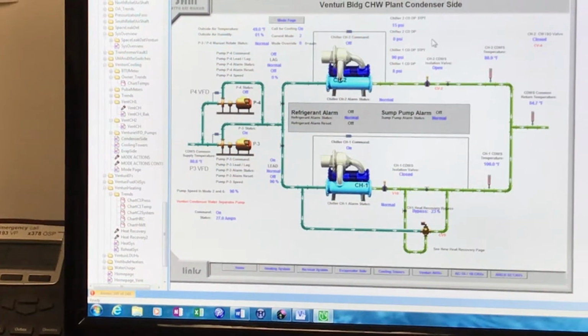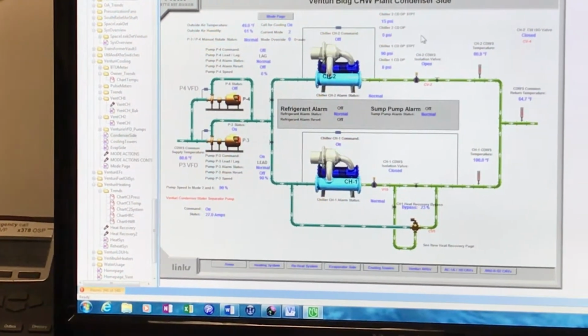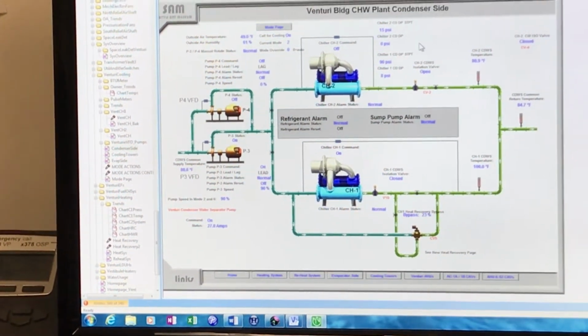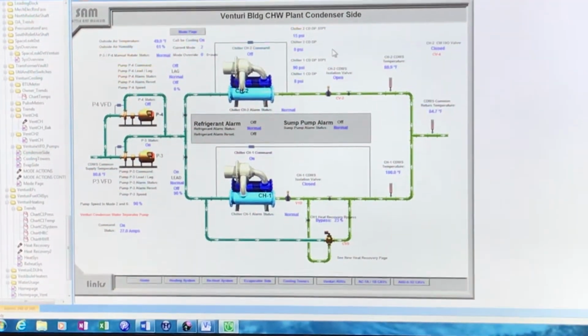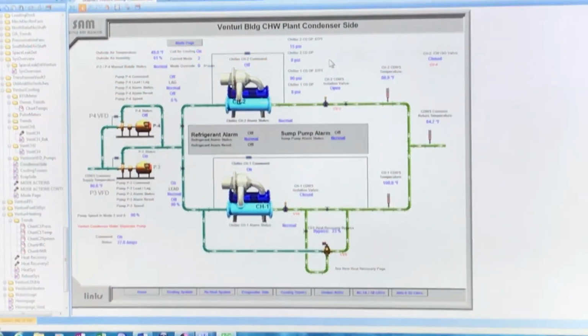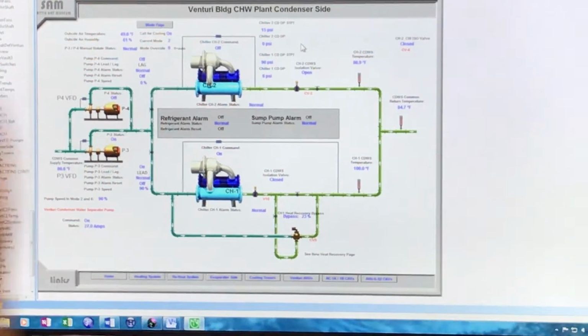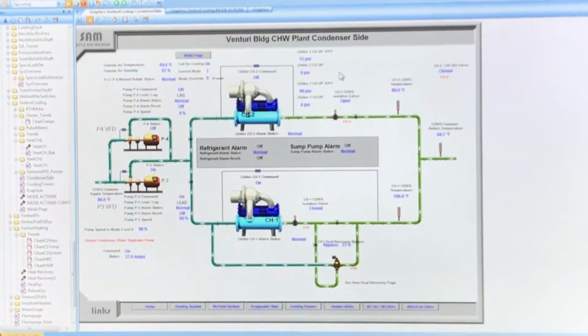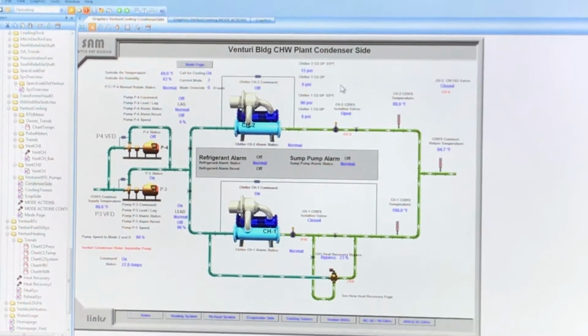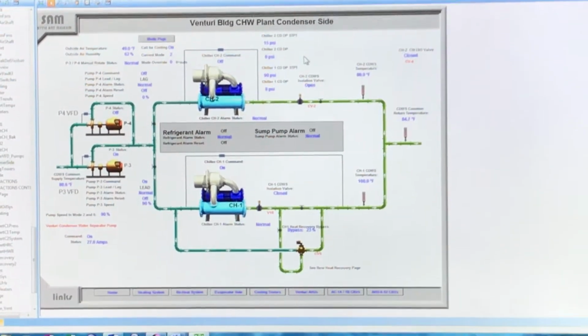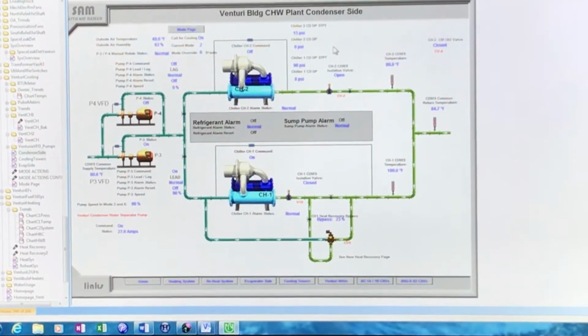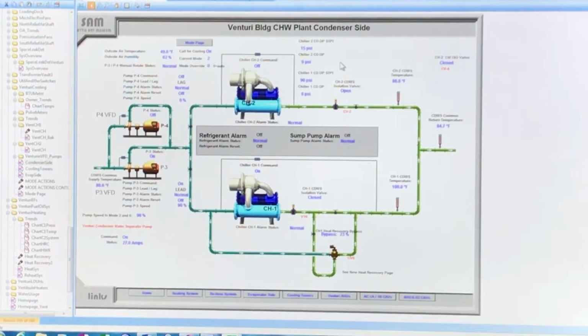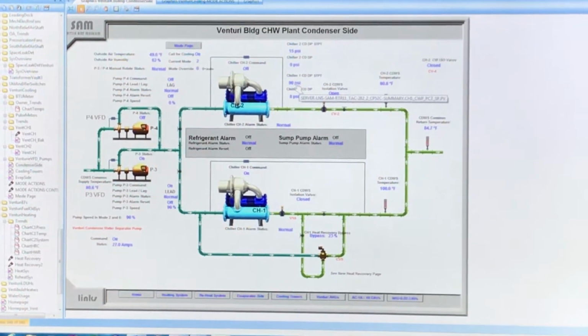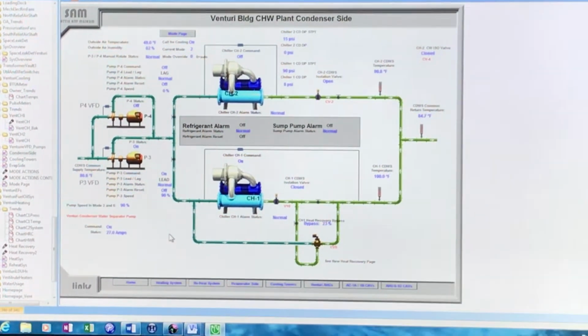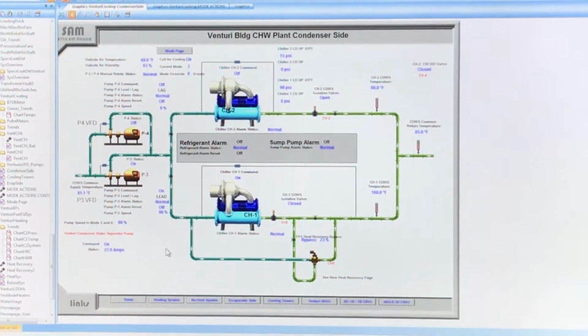So what you're saying is condenser 2's delta P is more important than condenser 1. Yes. What Bruce is trying to reiterate is, if you look at chiller number 2, the condenser is showing a delta P of only 15 psi. If you look at chiller 1, it's trying to go to 90 psi, but it's only showing 8 right now. So is the 90 psi just an arbitrary number? Yes. It's just so we can try to get 100% flow all the time. Okay.